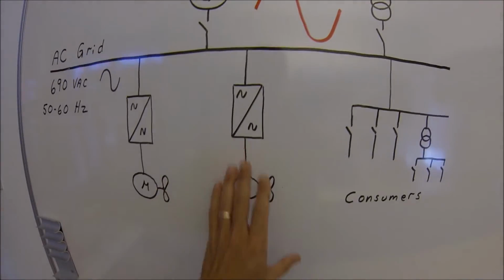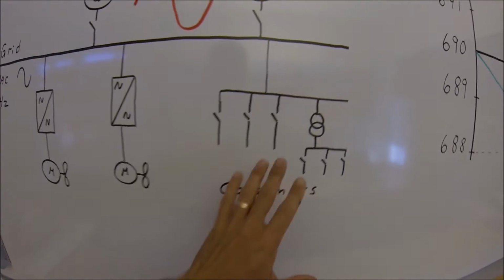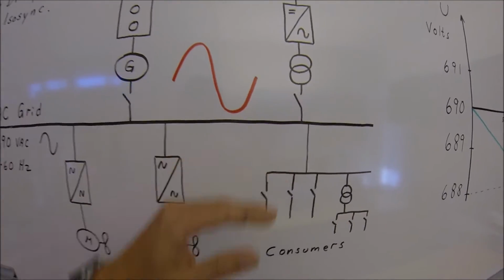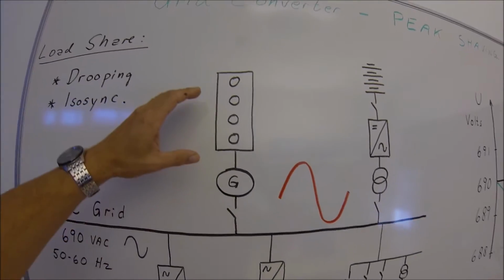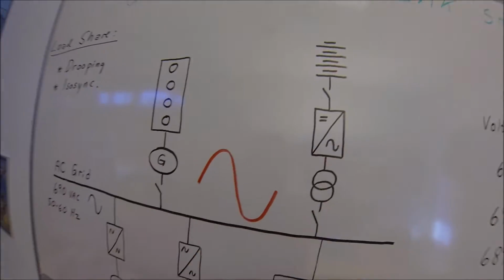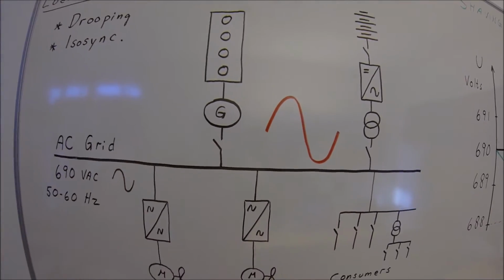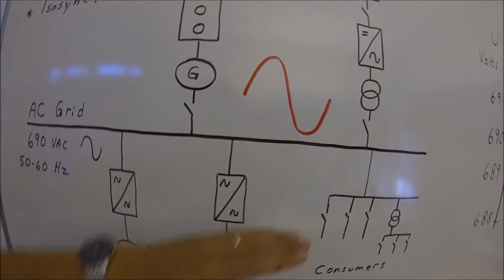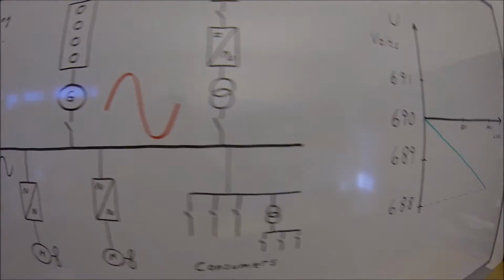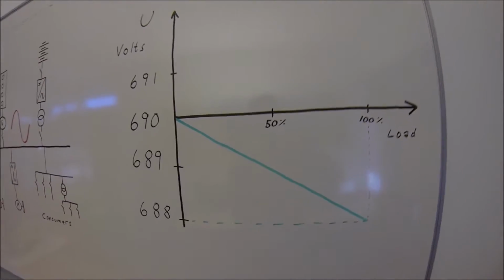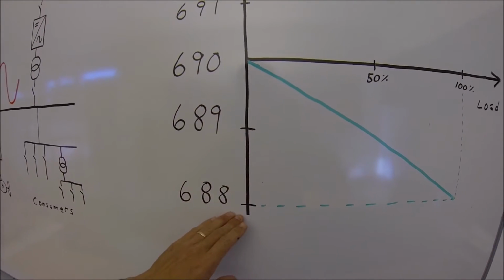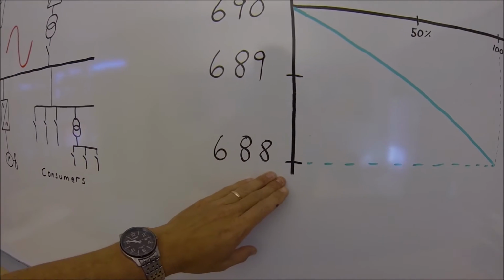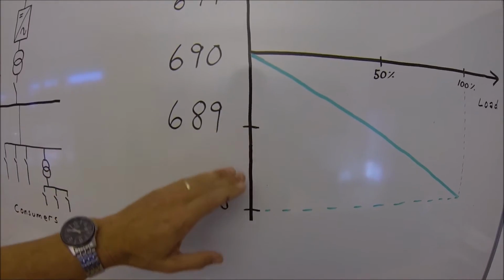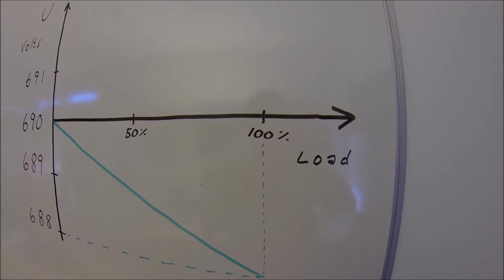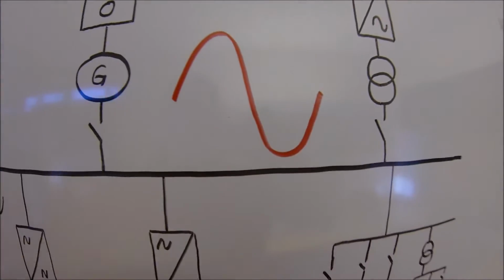Typically, when you have direct online start consumers, there is a big drop in the voltage, and the generators and the energy storage need to feed a lot of reactive currents just to keep the voltage up. And then the voltage drooping will determine how low the voltage will drop on the ship. If we make it too stiff, then the current can be quite big just to maintain the voltage on the grid.